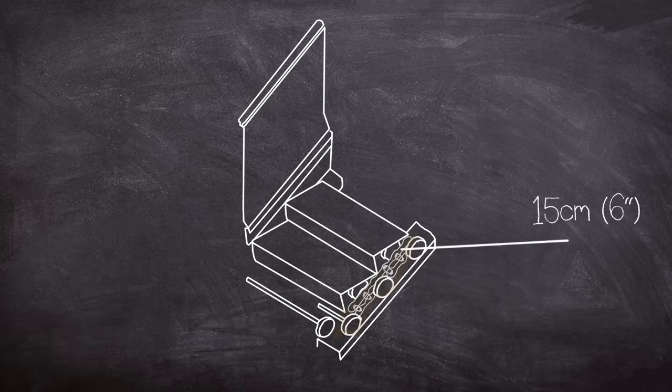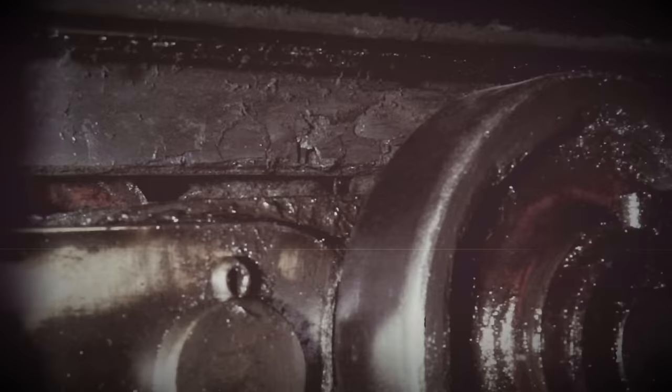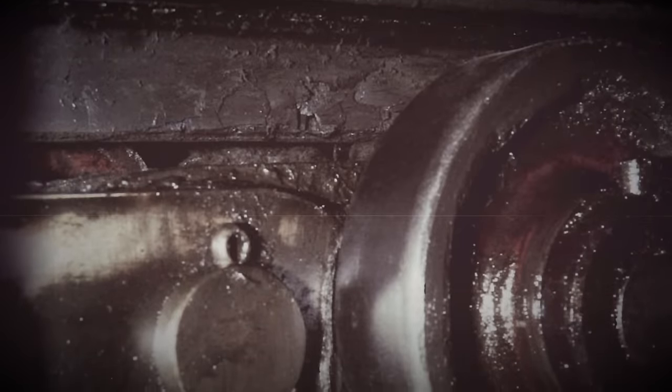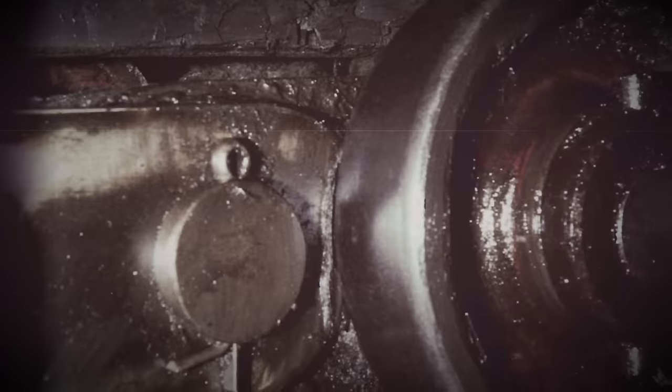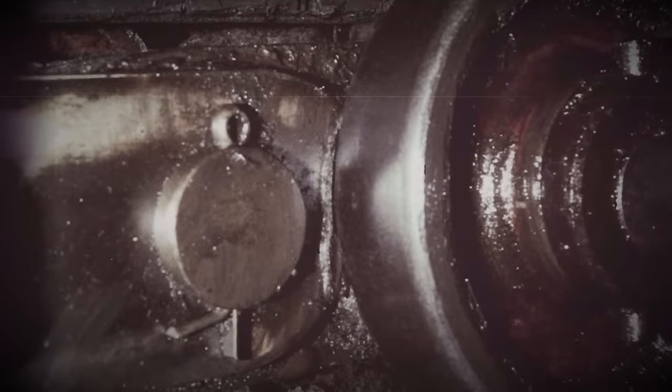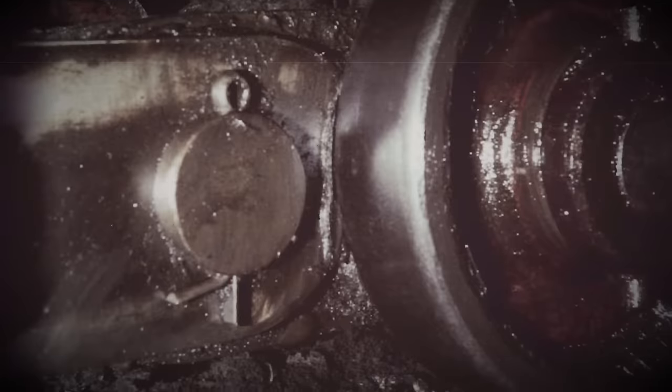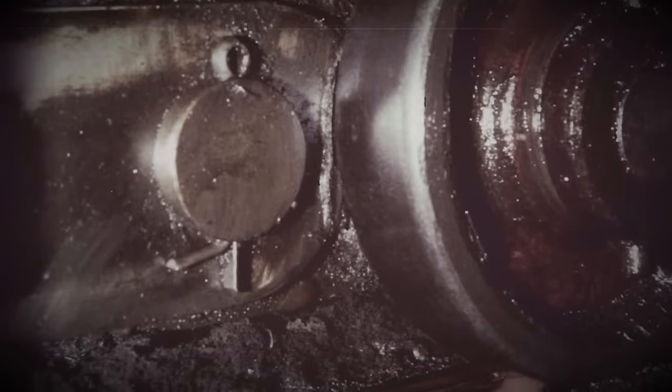There is a large gap of around 15cm between the two sets of wheels, giving enough space for large build up of grease and other debris, which due to the space once again is very difficult to remove. Such a build up is pretty much the perfect supply of fuel for a fire.